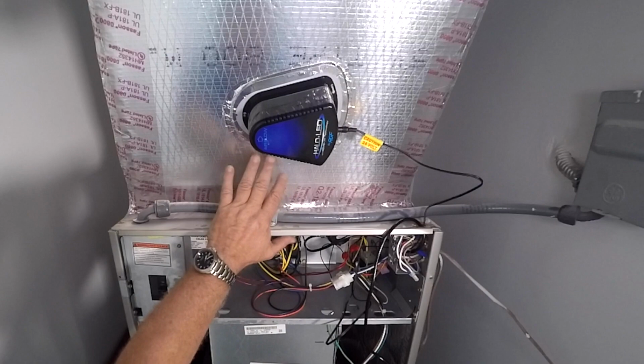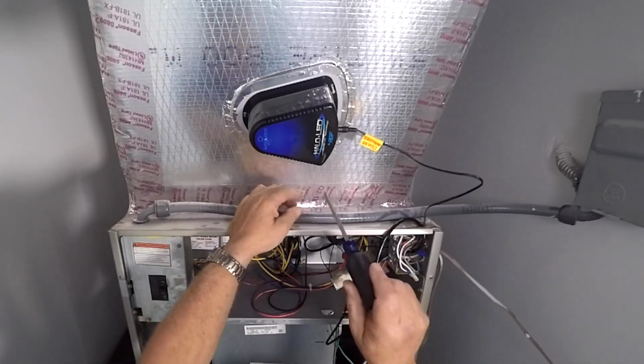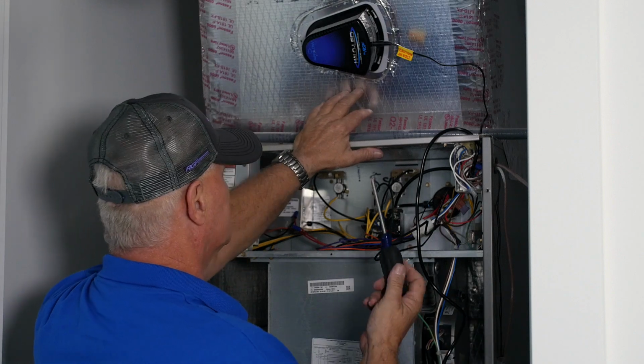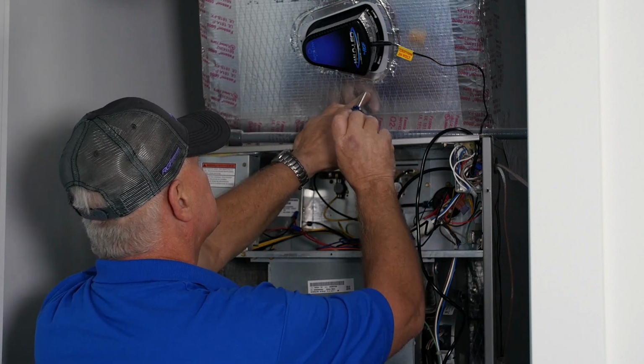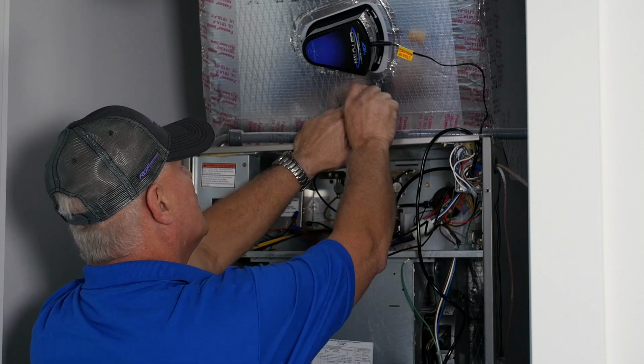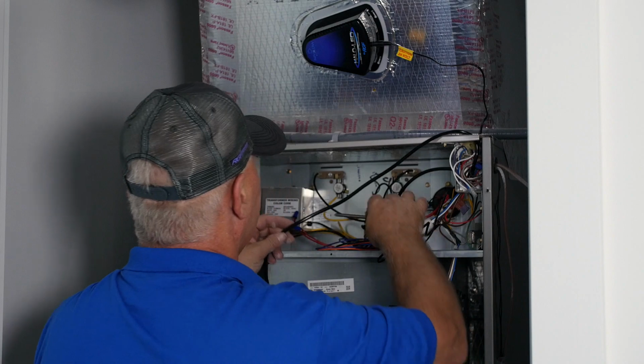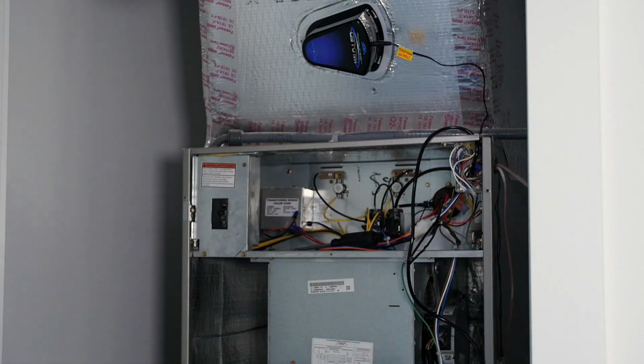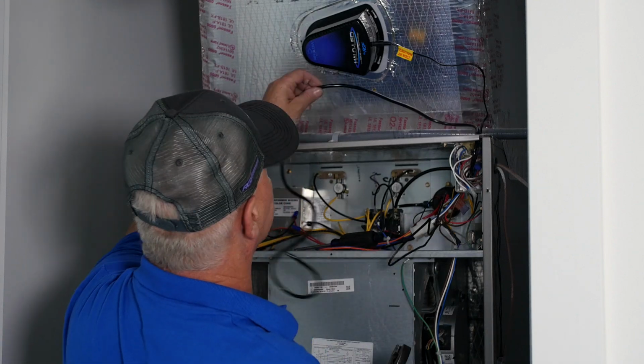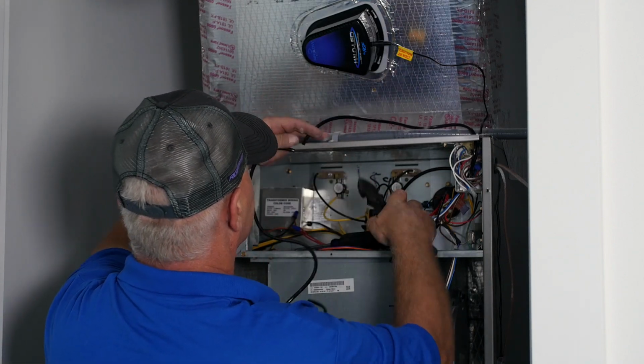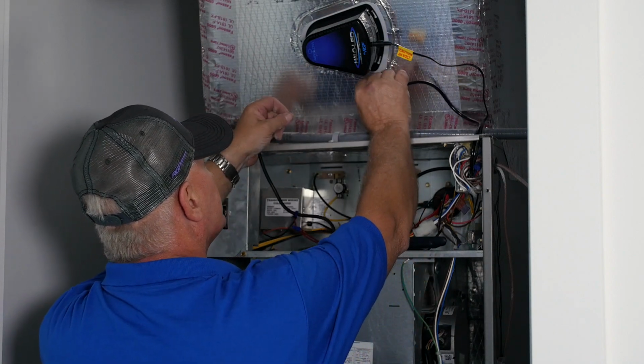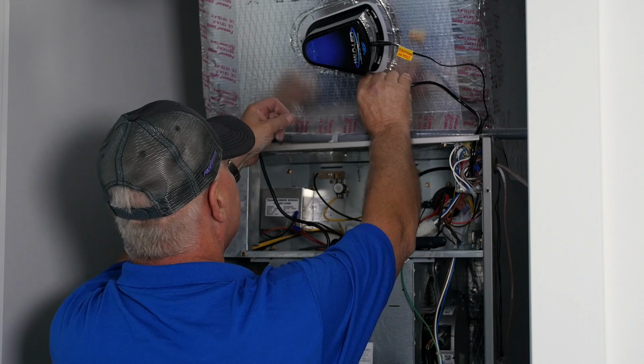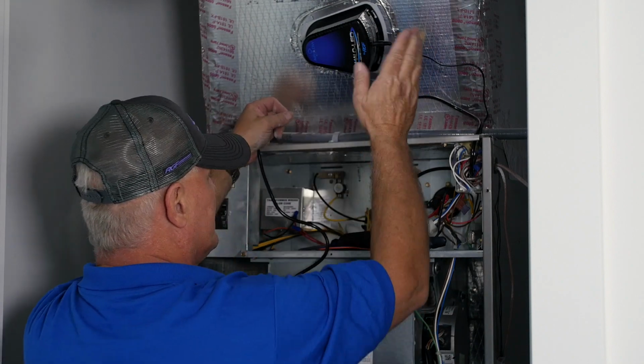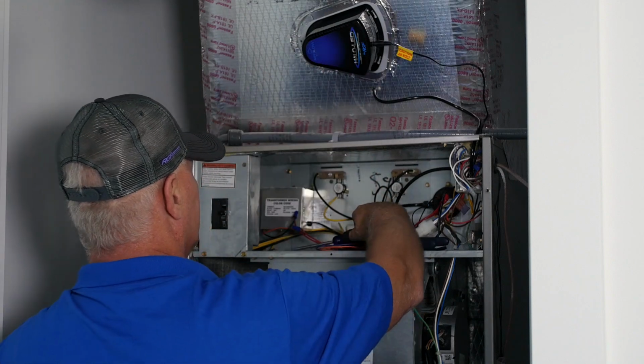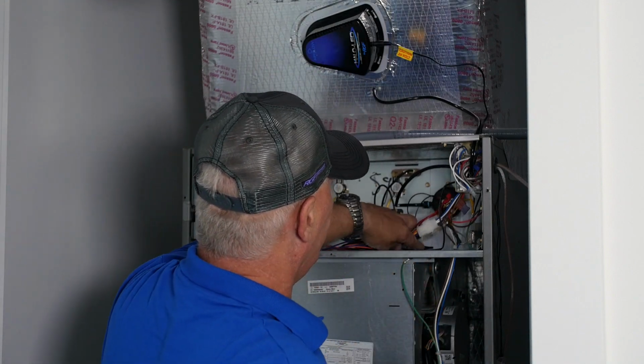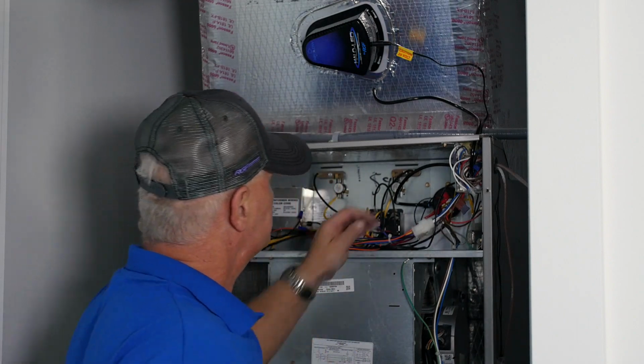What I prefer to do here is come up where my REME is to get my positive airflow side on this type of ductwork. Using a standard number 3 Phillips, I can just simply poke a small hole through the entire ductwork, and then I can trim my sensor tubing so it is not long and gangly, like so. Pop it through that hole, making sure you get it far enough to be inside and sense the pressure differential between here and there, the low side and high side. And that completes the install for this unit.